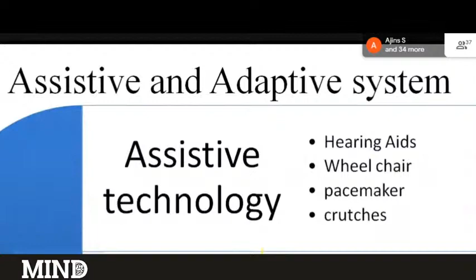So what is the difference between the assistive technology and adaptive technology? I have to state this with an example. Take the hearing aid and cochlear implants. The difference between the hearing aid and the cochlear implant is that the hearing aid just assists the human by simply amplifying the sound signal from the surroundings and then giving it to the eardrum. That's the duty of the hearing aid. But in the case of the cochlear implant, it simply bypasses the faulty portion of the ear and directly gives the amplified signal into the cochlear nerve of the ear, which is responsible for the hearing.